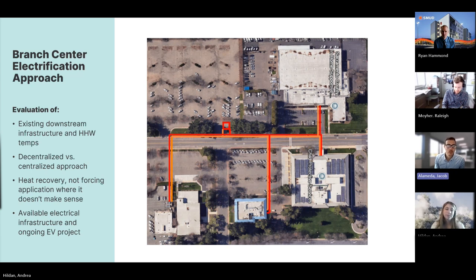Option 3 was what it looks like to put all of these on a central plant: take the chilled water from all these plants, shown in the square in the parking lot, identified as the best location in the middle of all the buildings for a central plant. There, put water-cooled chillers, cooling towers, and one large air-to-water heat pump plant to distribute heating water and chilled water to each plant.